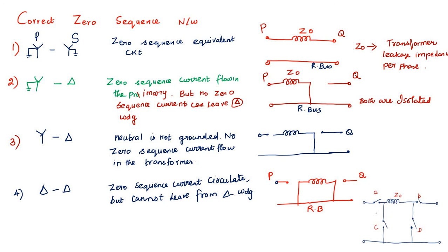In the general equivalent circuit, for case one where both sides are star grounded, A is closed and B is closed, while C and D are open. For case two, where primary is star grounded and secondary is delta, zero sequence current flows in the primary but no zero sequence current can leave from the star-delta winding. So A is closed, B is not closed, D is closed, and C is not closed.